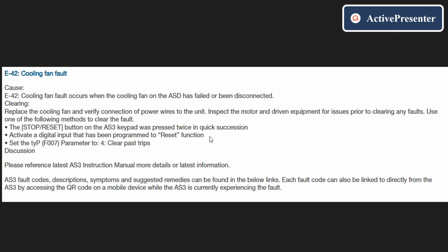So in that case, what could be the reason? In this case, the reason could be that the fan is faulty. What you need to do is just replace the fan, or you can verify the power wires of the fan to the PCB. Inspect if there is an issue when you replace the fan and it's still the same issue.